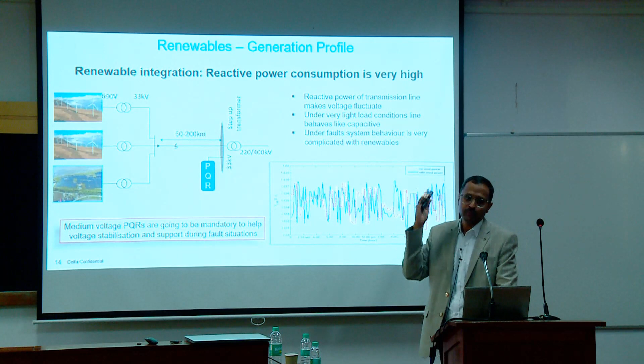Another approach that works best in India is this. Whether it is wind or solar, you always have a converter before you connect it to the 33 kilovolt grid. Whether solar or wind, it is fluctuating, as I mentioned. Let us take a 1 megawatt solar plant, which is always continuously fluctuating. It fluctuates almost full power in 4 seconds. This is a typical rate of change of power. 1 megawatt can change within 4 seconds, which is not good for the grid.